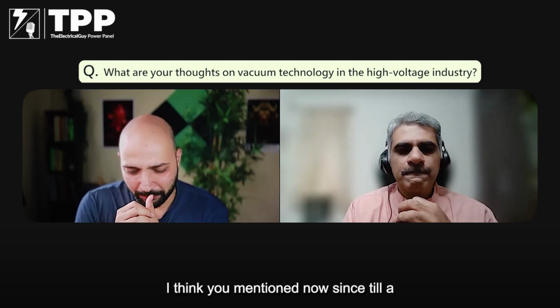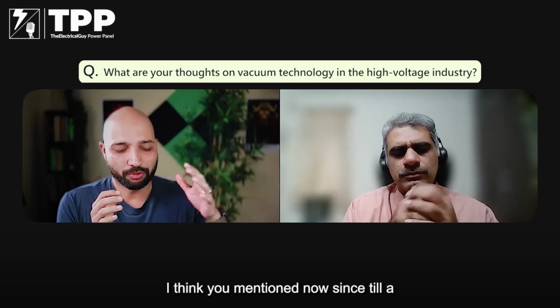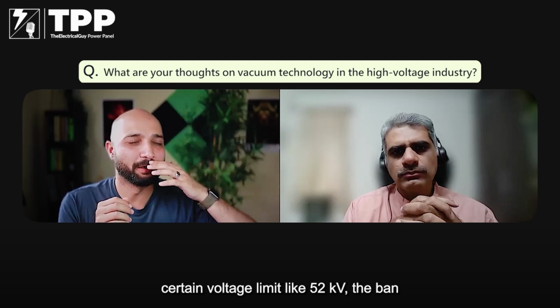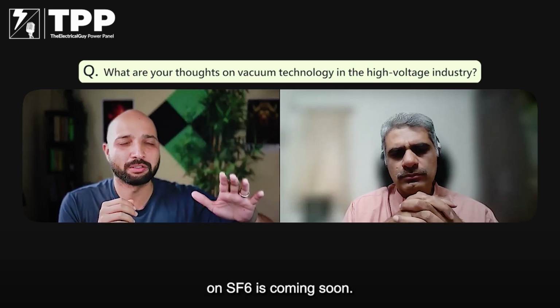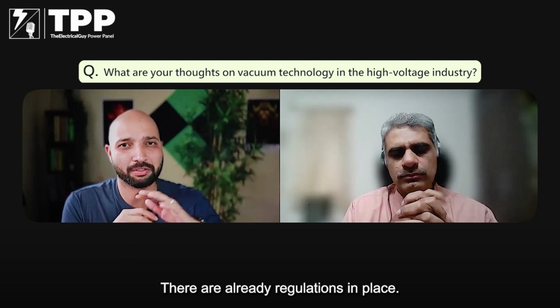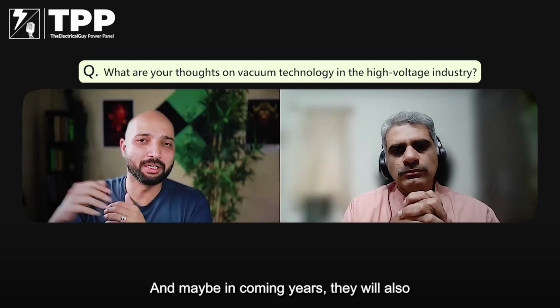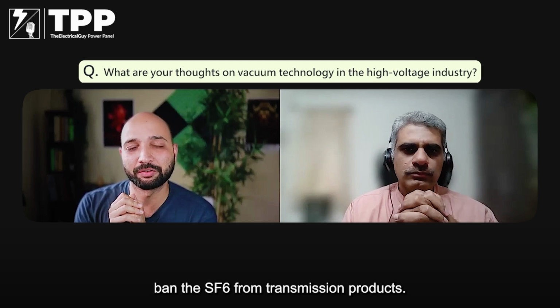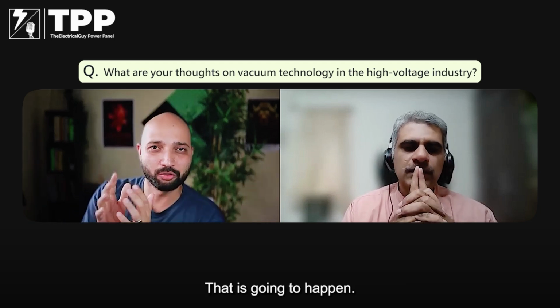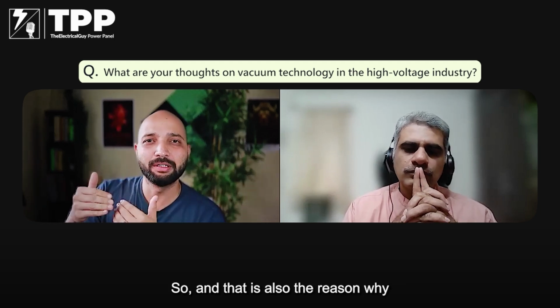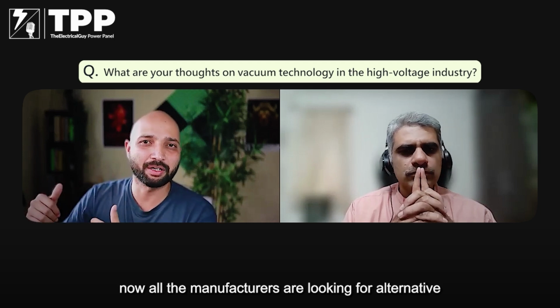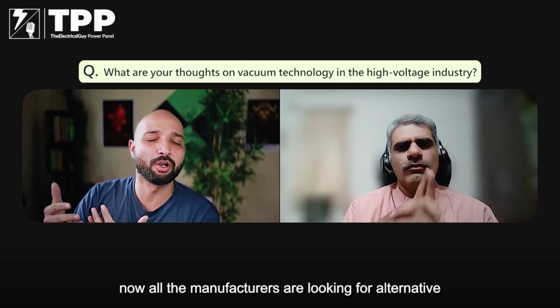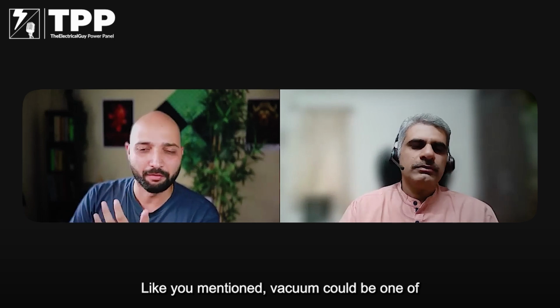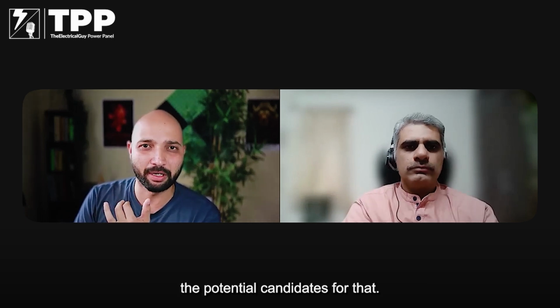True. I think you mentioned that up to a certain voltage limit, like 52 kV, the ban on SF6 is coming soon. There are already regulations in place, and maybe in coming years they will also ban SF6 from transmission products. Yeah, that is going to happen. And that is also the reason why all the manufacturers are now looking for alternatives to SF6. Like you mentioned, vacuum could be one of the potential candidates.